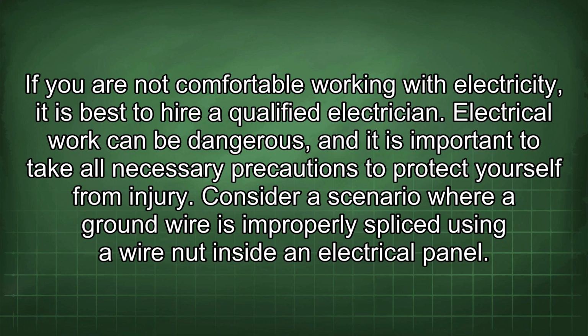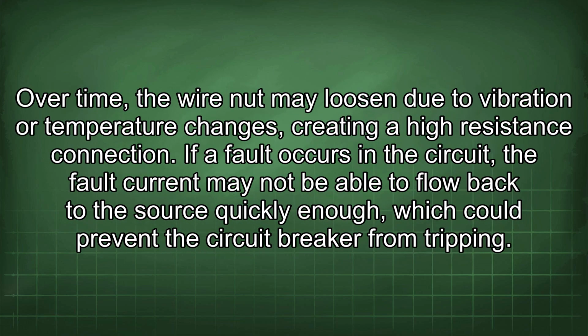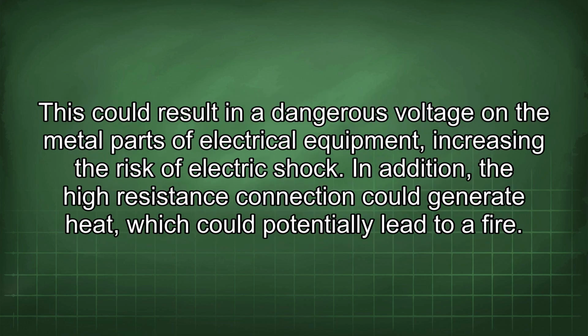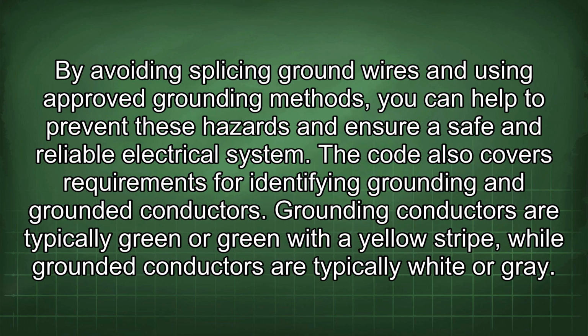Consider a scenario where a ground wire is improperly spliced using a wire nut inside an electrical panel. Over time, the wire nut may loosen due to vibration or temperature changes, creating a high-resistance connection. If a fault occurs in the circuit, the fault current may not be able to flow back to the source quickly enough, which could prevent the circuit breaker from tripping. This could result in a dangerous voltage on the metal parts of electrical equipment, increasing the risk of electric shock. In addition, the high-resistance connection could generate heat, which could potentially lead to a fire. By avoiding splicing ground wires and using approved grounding methods, you can help to prevent these hazards and ensure a safe and reliable electrical system.